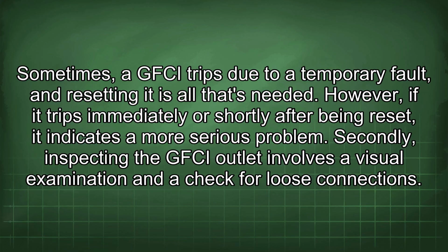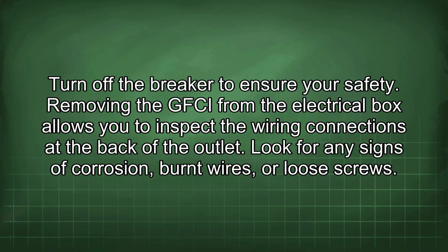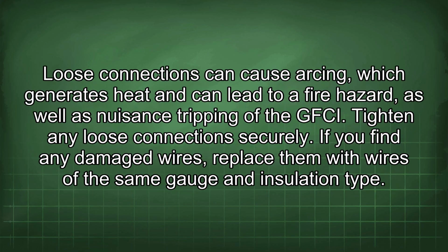Secondly, inspecting the GFCI outlet involves a visual examination and a check for loose connections. Turn off the breaker to ensure your safety. Removing the GFCI from the electrical box allows you to inspect the wiring connections at the back of the outlet. Look for any signs of corrosion, burnt wires, or loose screws. Loose connections can cause arcing, which generates heat and can lead to a fire hazard, as well as nuisance tripping of the GFCI. Tighten any loose connections securely.